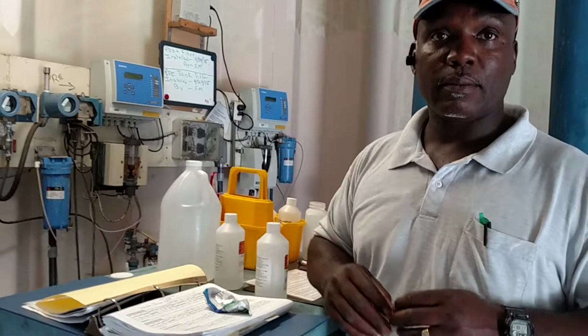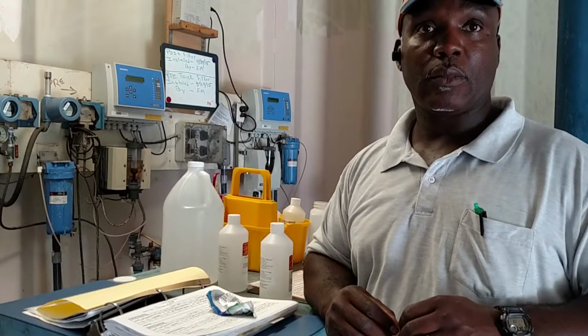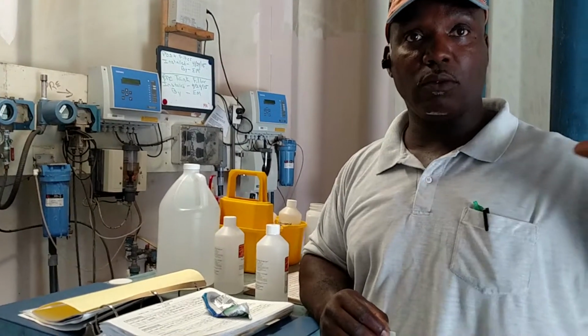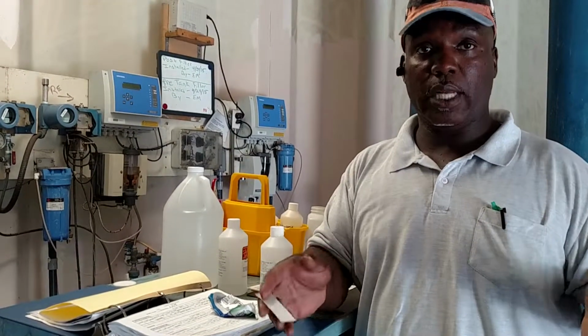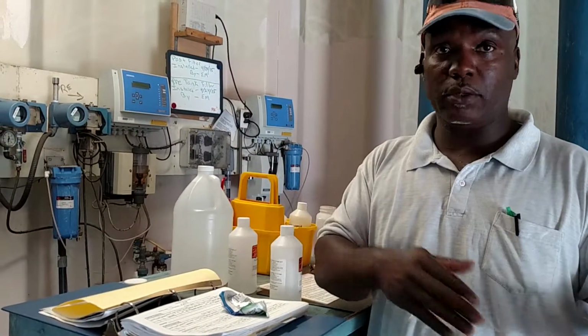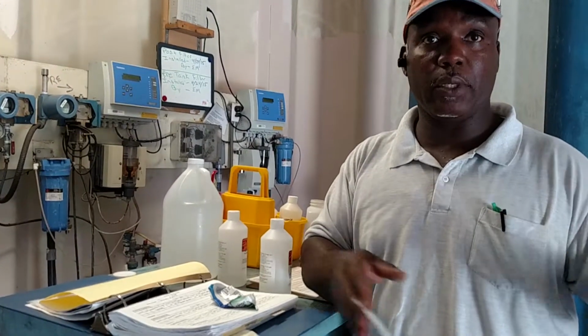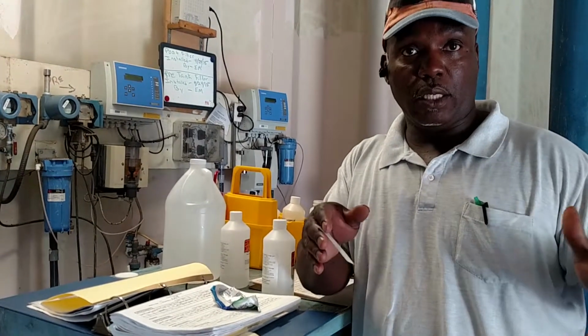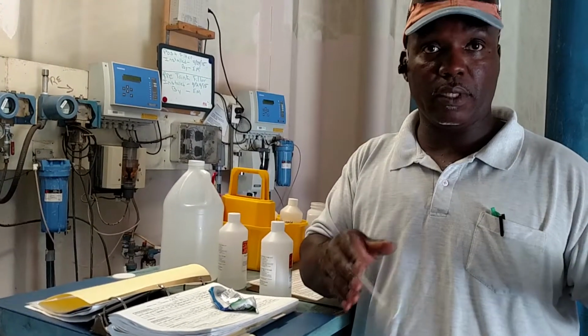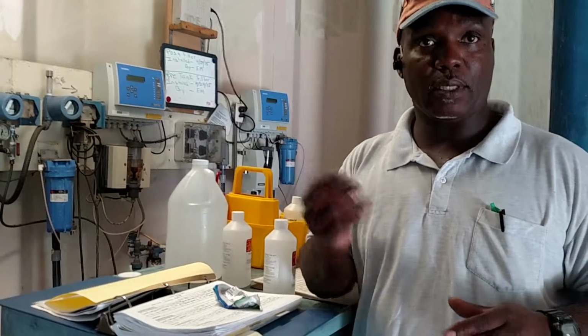And do you visibly see something on the tip that tells you you need to clean it? When it doesn't calibrate, you'll see that, most of the probes are like that. It takes a long time for it to get to the set point. Sometimes it doesn't even move at all. Okay. But on the good ones, most of the time, you put a 0.2 in there, it goes almost immediately to a 0.2. You put a 2.0 in there, it automatically goes to a 2.0. Okay. But when it starts slowly drifting up or down, wherever your standard is, that's when you want to go ahead and calibrate. Condition, they call it condition, your probe.